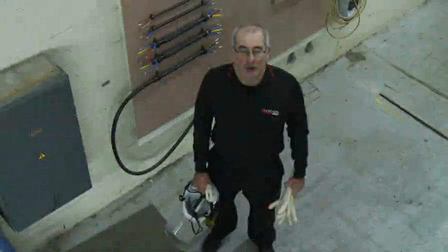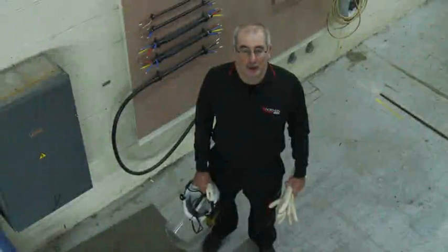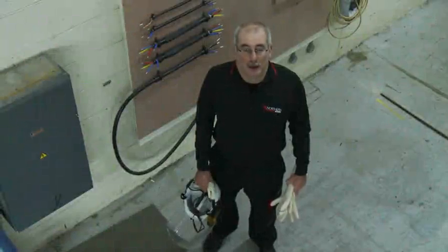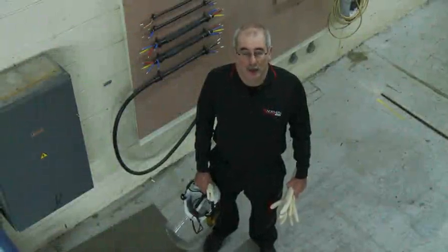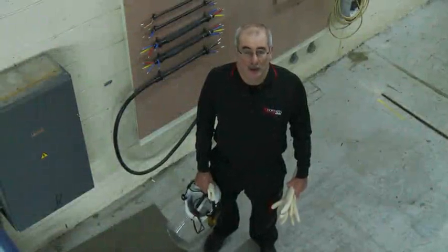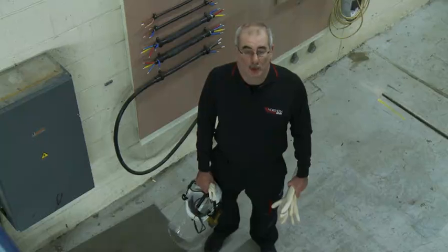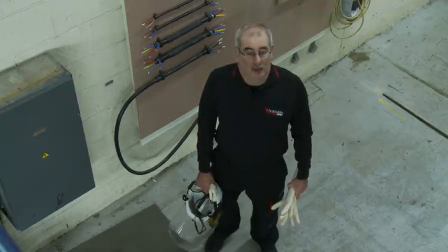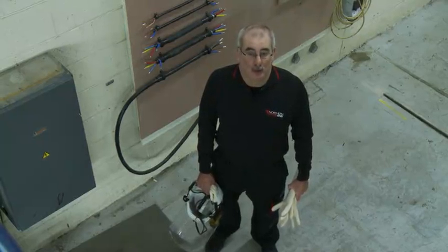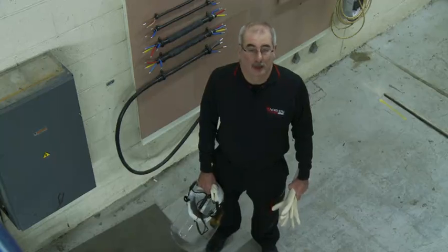The arc flash protection afforded by the new PPE system is based on the layering system. When you are out on the network working live, you'll be required to wear either a 0, 1 or 2 layer option. 1 layer, such as this, will afford over 9 calories of protection, while if you double that, it's an exponential rule which will afford over 30 calories of protection.